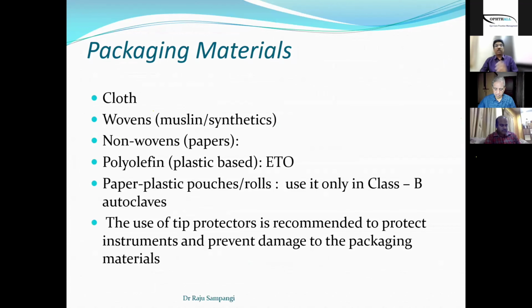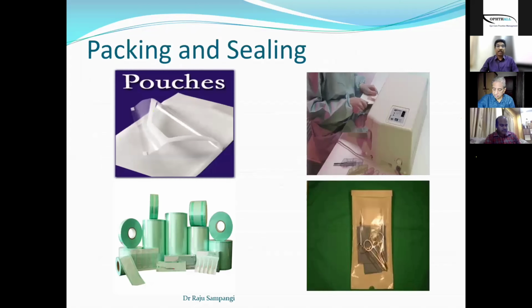So after you've cleaned, then you need to package them. So use the correct packaging material that is required for the autoclave that you're choosing. Not only the packing, you also have to use the correct sealing machine, because if you are using a class B autoclave, there's a lot of pressure being generated. I'll show you in the videographs subsequently why it is important to have a correct sealing machine also.